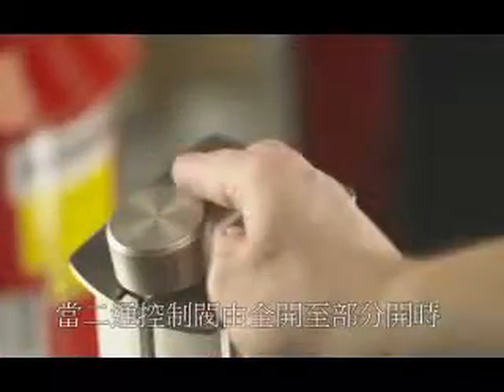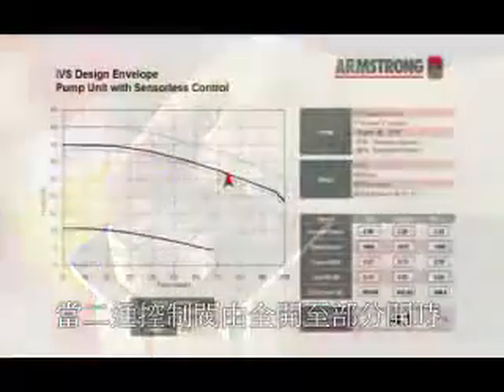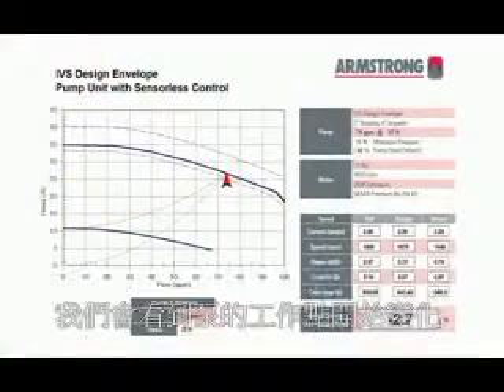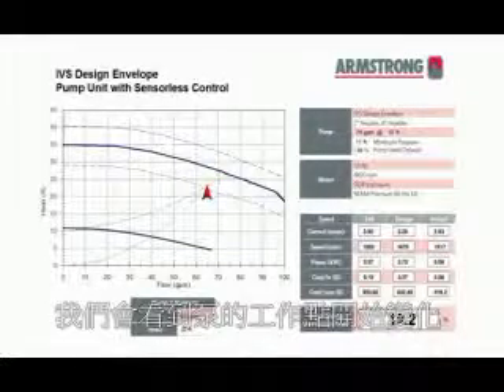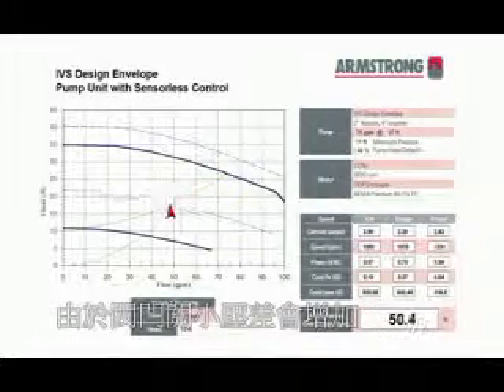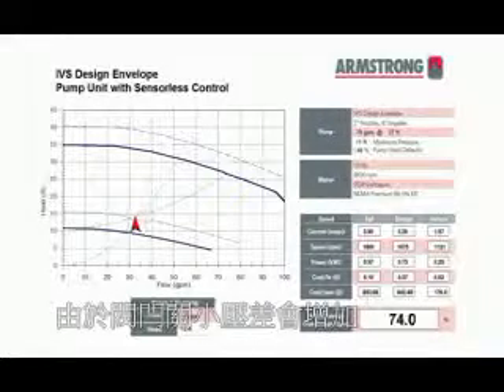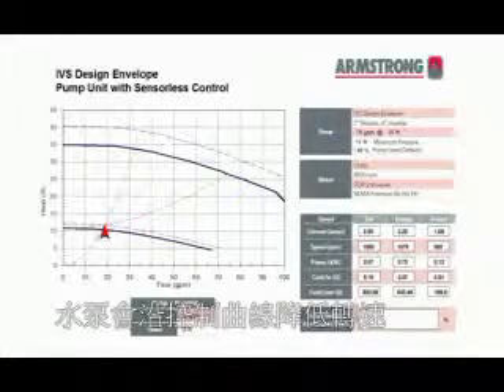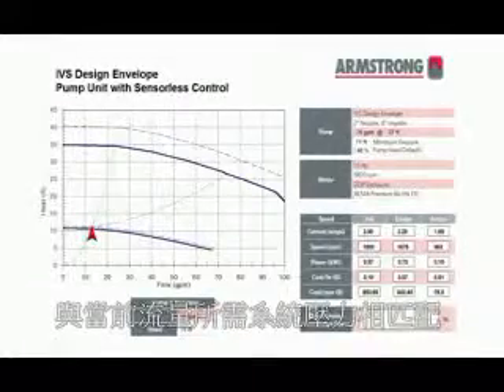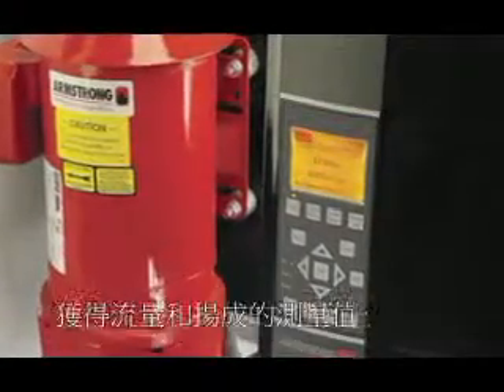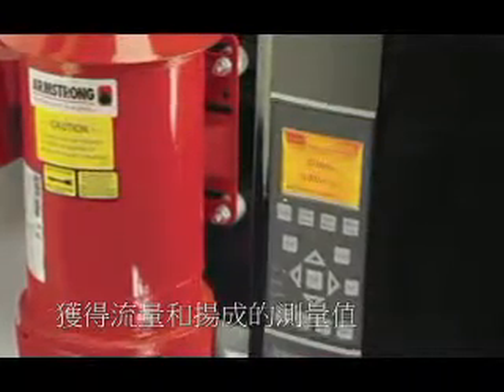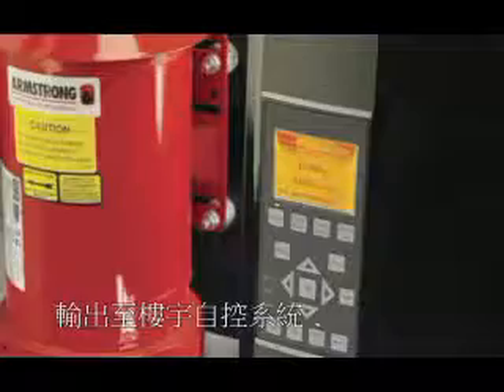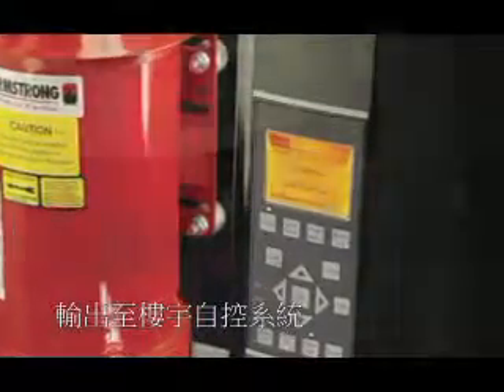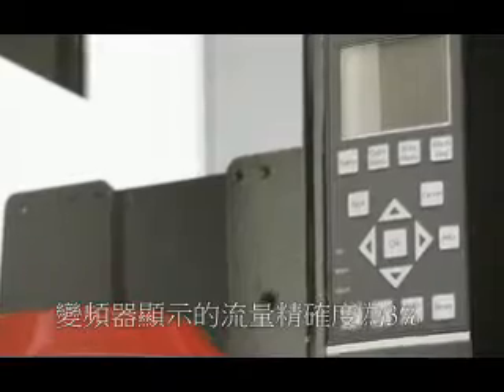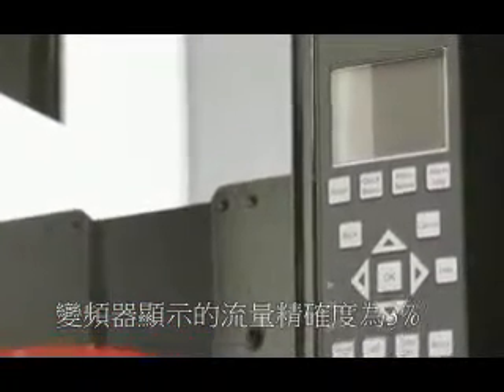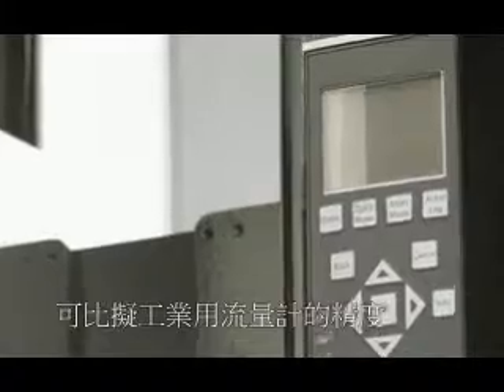As we begin to throttle the two-way control valve from the fully open position, we can see the quick responsiveness of the sensorless control. We can see the duty point of the pump begin to change. As the differential pressure across the valve increases, the pump reduces in speed following its control curve to match the required system pressure at the current flow. Flow and head measurements are available on the IVS keypad display. It's also possible to export these values to the building automation system. The flow display that is inherent to the drive has a 3% accuracy level at part load. That rivals industry flow meters.